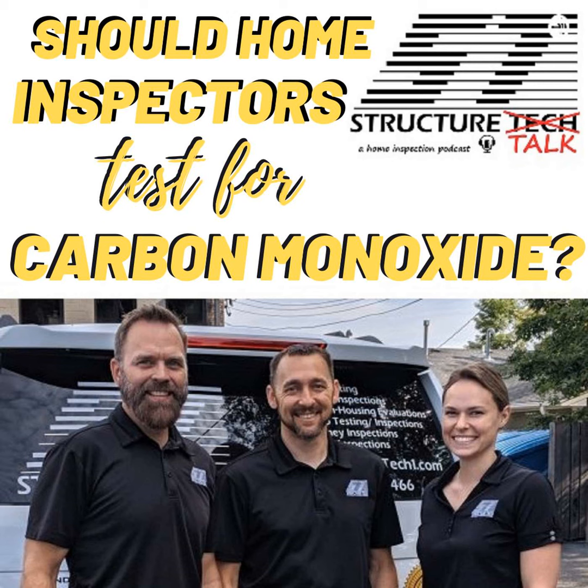But if you have a fancier combustion analyzer, it actually does a calculation and figures out how much free air you have in here. Then it subtracts all of that air to give you the actual number of the CO that's coming out of the flue undiluted. So it's giving you a much more accurate number. It's the air-free number, and that's the number that's referenced in the code. So if you're just taking a plain old CO tester and it can't do that calculation, you don't know. All you can do is guess.